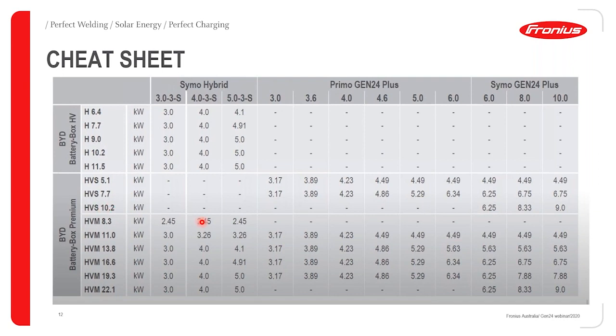Now, one thing which is similar, if you go maximum storage with the HVS and maximum storage with the HVM, the amount of power you can discharge will be the same. So for example, if a customer goes for a 10.2 HVS, he can discharge or charge the battery with 9 kilowatt on a Symo 10. If they go with an HVM 22 kilowatt hour, they can do the same, discharge or charge using 9 kilowatt.